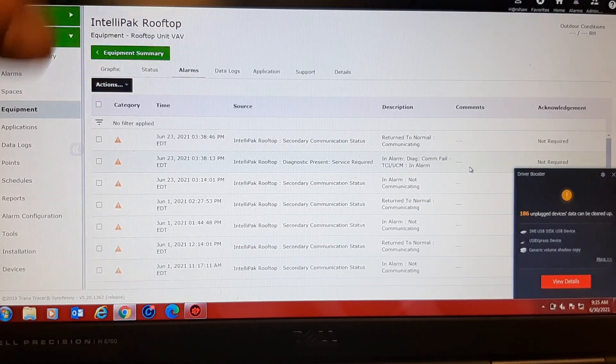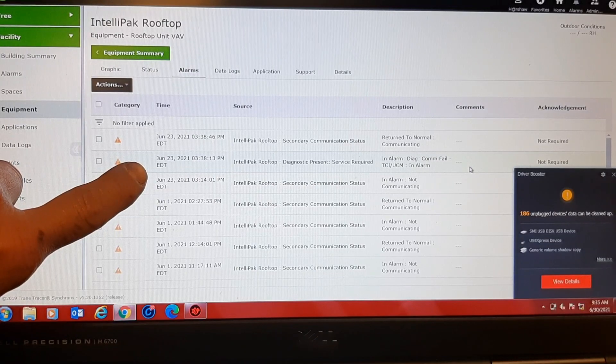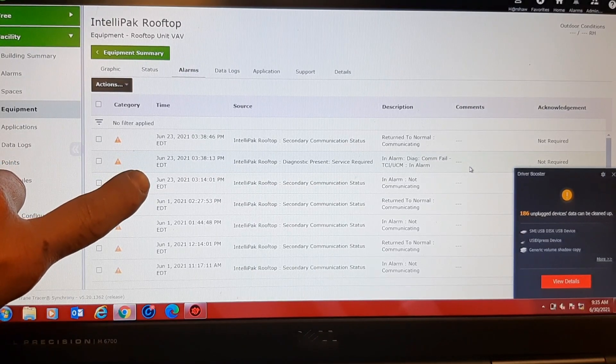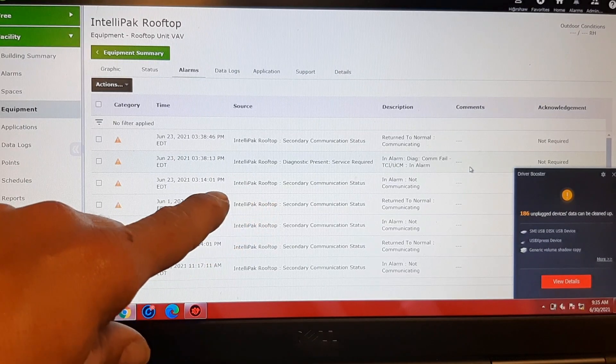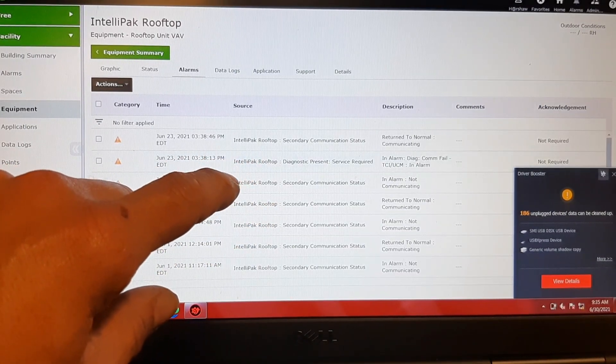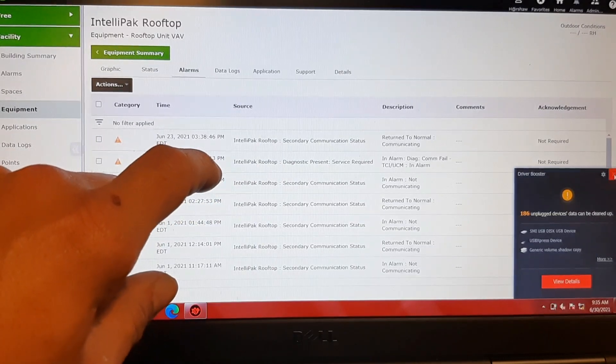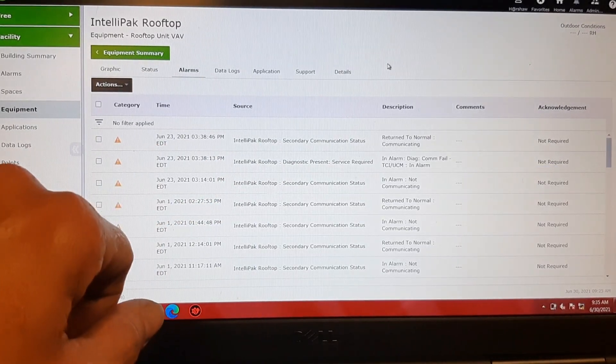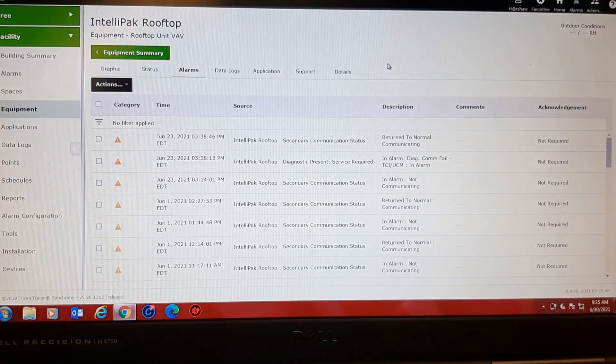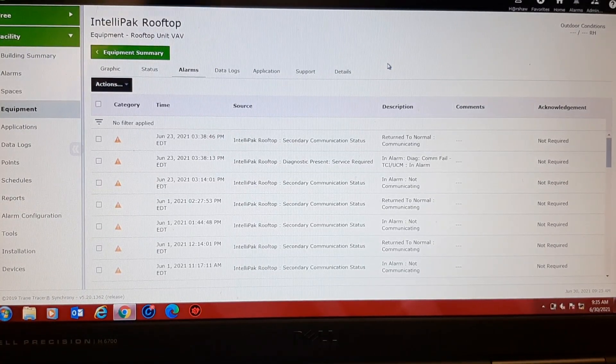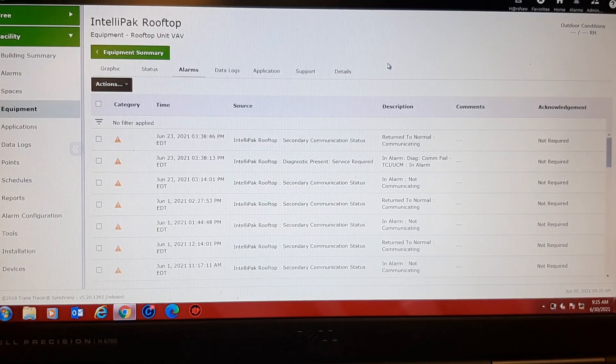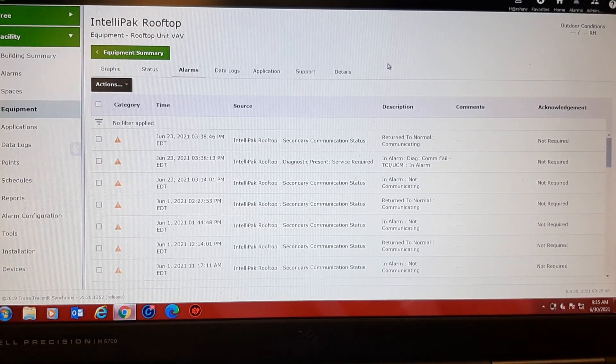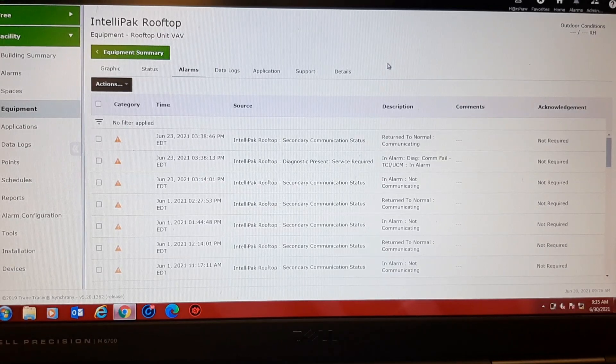Well, at least the 23rd might have been out doing a PM or something. It's just not communicating. We do have old and new devices on this system. But I haven't had too many issues out of it. They remodeled one area and put new VAV boxes in. All the old VAV boxes are still installed.